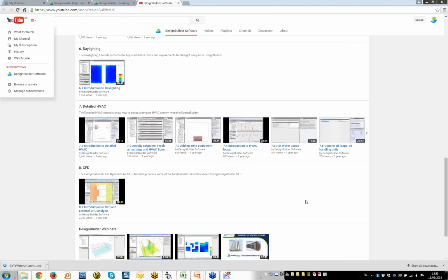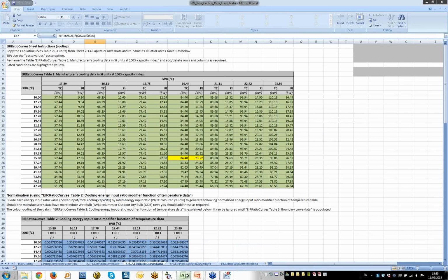What data was used to generate the LG Trane VRF curves? That was tabular data accessed from LG Trane websites. So the process that Dave mentioned within the spreadsheets, there are mechanisms that we provide to allow you to paste the tabular data into a spreadsheet in a particular format, and then you can copy that over into this spreadsheet, which actually generates the coefficients.